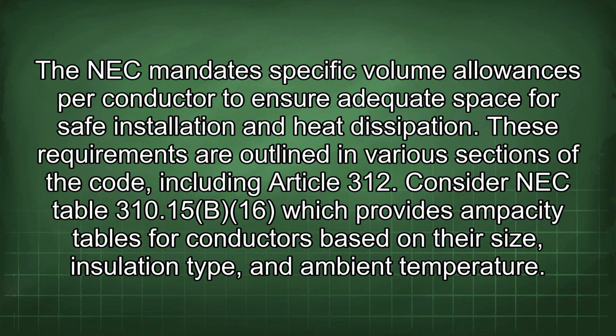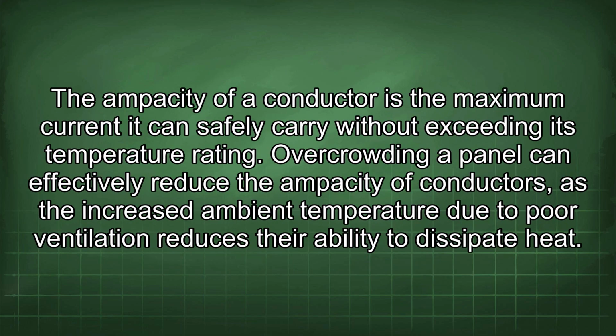The NEC mandates specific volume allowances per conductor to ensure adequate space for safe installation and heat dissipation. These requirements are outlined in various sections of the code, including Article 312. Consider NEC Table 310.15(B)(16), which provides ampacity tables for conductors based on their size, insulation type, and ambient temperature. The ampacity of a conductor is the maximum current it can safely carry without exceeding its temperature rating. Overcrowding a panel can effectively reduce the ampacity of conductors, as the increased ambient temperature due to poor ventilation reduces their ability to dissipate heat.